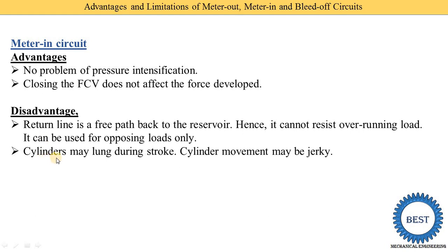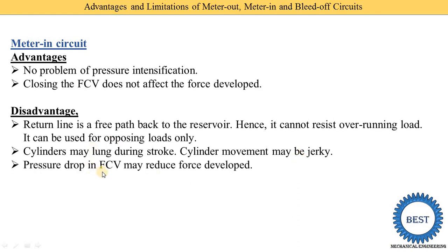Second disadvantage: the cylinder may lunge during strokes and cylinder movement may be jerky. Also, pressure drop in the flow control valve may reduce the force developed — when pressure is reduced in the flow control valve, the force developed is reduced.